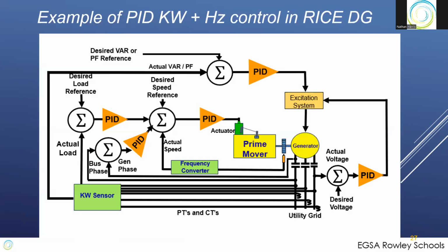I'll show you one here, and this is just one. There's a bunch of them, but this is probably the most complicated, and we'll sum up the regulators. If we're driving the generator over here on the right side with the prime mover, we're checking frequency here, and we have a speed control with the desired speed reference, 60 hertz generally in our industry, a PID regulator, which drives an actuator, which drives that prime mover. So here your primary initial loop is speed.